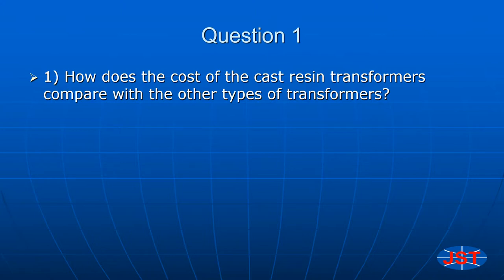And again, that depends on a lot of things, but that's just a general guideline. For VPI, I would say you're looking at about a 10% difference. And when I say differences, those are all lower cost. Remember, cast is generally a little bit more. However, I can say this, depending on some units, when you look at things that come out of our factory, where there's a lot of economies of scales, I've even seen some cases where the price tag with VPI was right in line, and pretty close to oil filled as well. So it depends on a lot. But in general, that's what I would say. For oil filled, you're looking at an initial price tag that's about 15 to 20% less than cast. And for VPI, around 10%, maybe that percentage is even a little bit lower than 10.